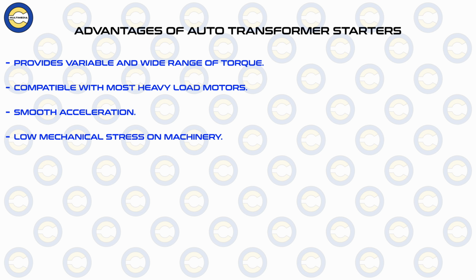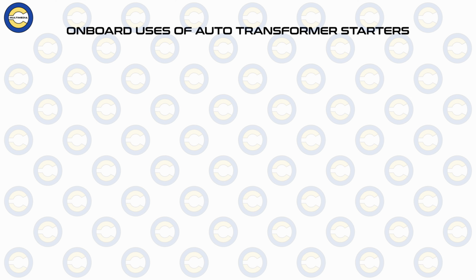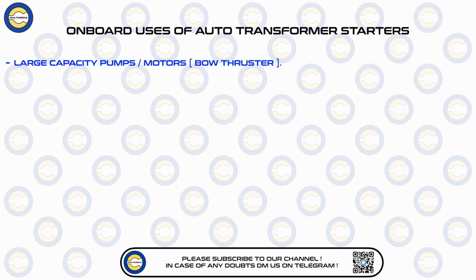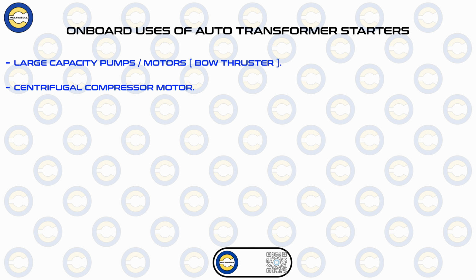So now another common question would be, where can these types of starters be used on ships? Wherever we have very large capacity blowers and pumps, or for example the bow thruster motors, is where these types of starters would find their premium application. And even in ships where there are centrifugal compressors, these are the starters that you would commonly find. And with such large scale implementation, and because they are being used on very important machinery that draws a very high supply value and also supports heavy loads, it is very important that we carry out regular checks and whatever possible maintenance on board for such starters.